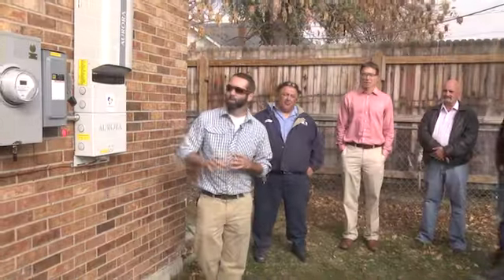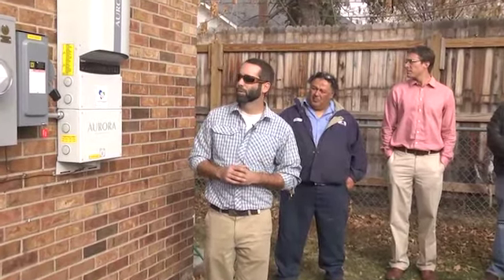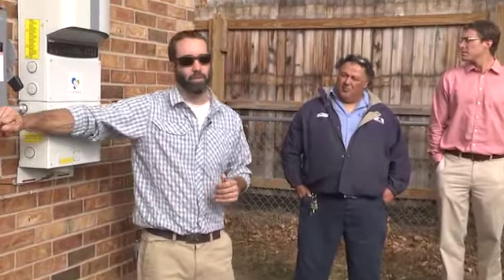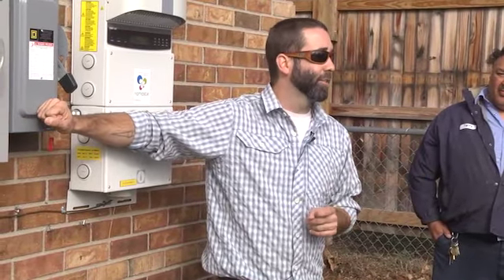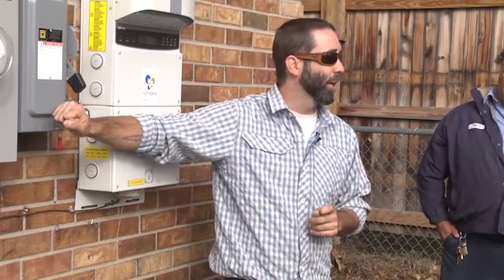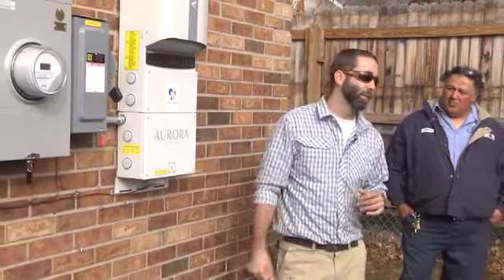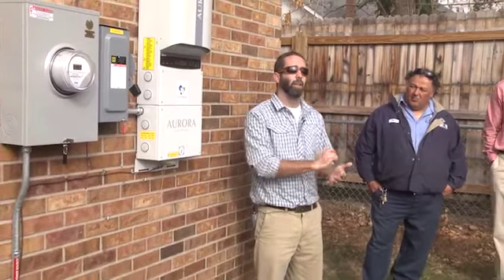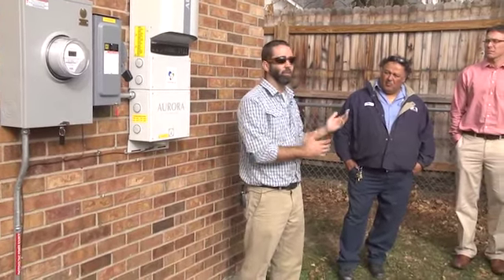It may be best practice to start from the AC side, because the inverter needs that grid voltage to function. If you hit it with the AC first, it'll start waking up, and then you hit it with the DC, but ultimately it doesn't matter. When you walk up to it and it's reading error, it's important to make sure that both switches are in the on position. That includes the switch on the inside, if there's one on the inside. If all three, the two AC disconnects and the DC disconnect, are on and it's reading an error code, go ahead and jot that down and communicate upstream.